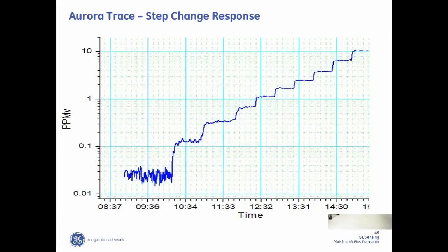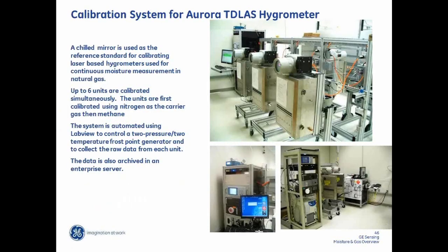And again, a similar process on our calibration systems. We do quite a bit of automation. These units have digital interfaces that are bussed in, and the calibration system is completely automated for these laser systems. We're often calibrating in natural gas, or if it's a gas mixture that deviates from what we consider to be standard natural gas, we can reproduce that mixture by mixing pure gases together and using that as the background gas for calibration. We feel it's always better to calibrate in something close to the process gas you're using than to calibrate in an inert gas.